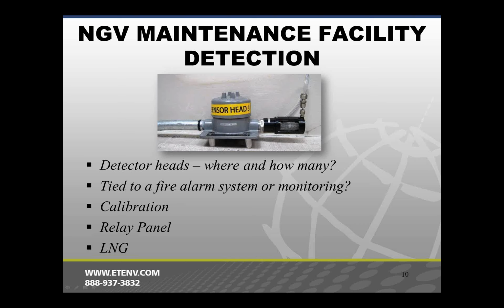What we usually end up with, sometimes it's integral to the gas detection system, and sometimes it's an add-on, is a relay panel. This relay panel can do as many things as you want it to, but what it has to do is sound alarms, turn off the heat, and turn on the ventilation system. And in addition, you can have it do things like open garage doors for fresh air intake. You could have it turn off your welding circuits, not a code requirement, but maybe an owner preference.